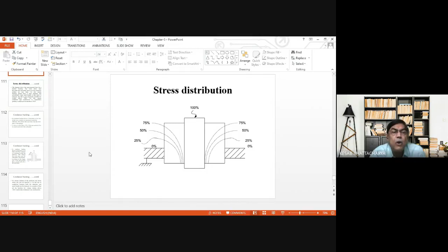Actually, I should not say field lines, these are equipotential lines. The 25% line is very close to the earth plate, and other lines like 10%, 15%, 5% will be almost touching the earth. In order to distribute the field lines or equipotential lines, condenser bushings are used. In a condenser bushing, aluminum or tin foils in the form of cylinders are introduced inside the dielectric. This reduces the axial stress near the earth plate of the bushing, as shown in the figure.